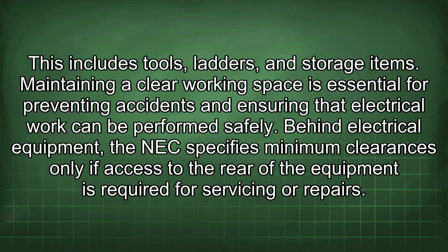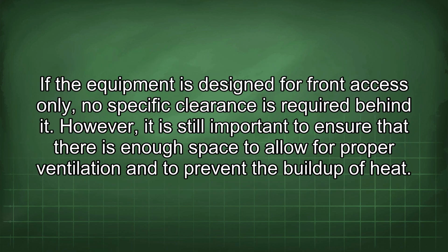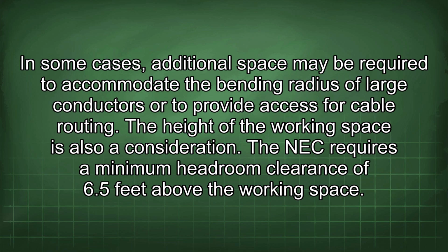Behind electrical equipment, the NEC specifies minimum clearances only if access to the rear of the equipment is required for servicing or repairs. If the equipment is designed for front access only, no specific clearance is required behind it. However, it is still important to ensure that there is enough space to allow for proper ventilation and to prevent the buildup of heat. In some cases, additional space may be required to accommodate the bending radius of large conductors or to provide access for cable routing.